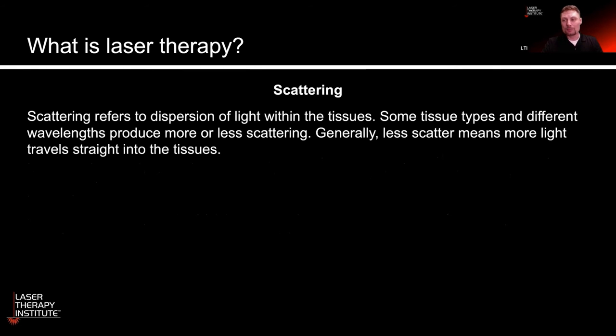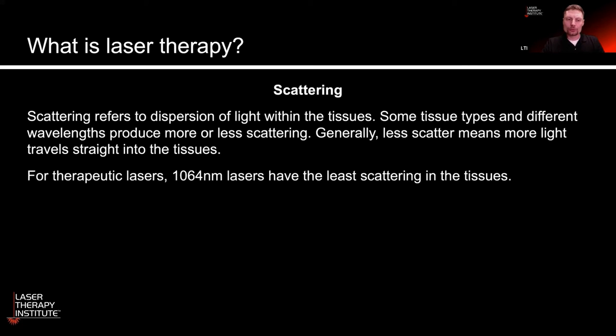I want to talk about scattering, because scattering means you're dispersing light into the tissues, and this can be a good thing because you're getting more dispersion around your laser beam into the soft tissues. Some tissues have more scatter than others — more water-containing tissues have less. Also, 1064 nanometer lasers seem to have the least amount of scattering in the tissues, so in many cases you can get 1064 in fairly deep because it doesn't scatter — it travels more in a linear fashion.